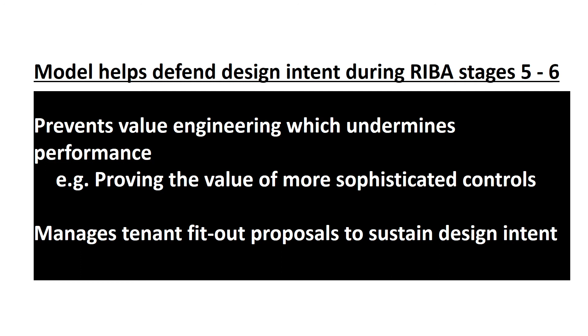Again, the model can support commissioning and tuning up of the building. If you know how much energy is supposed to be used by a specific sub-meter over a month at a particular time of year, and that amount of energy in practice is well above what it should be, that is a very big signpost to looking at what is going on, because the model is good enough to predict exactly how much energy that sub-meter should be showing.